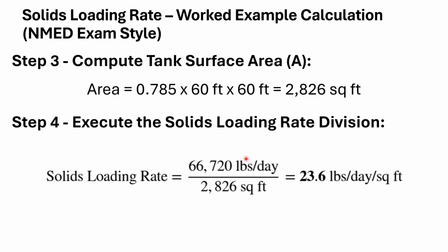And then your solids loading rate, you take that 66,720 pounds per day for your solids, and then you divide that by the area you came up with of 2,826 square feet. You end up with 23.6 pounds per day per square foot. That's your solids loading rate. That's the amount of solids per day coming in per square foot of surface area of that clarifier.